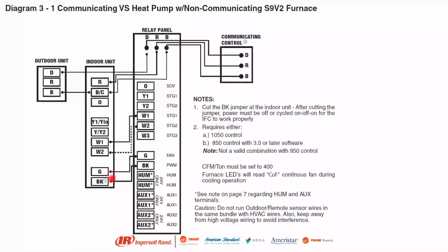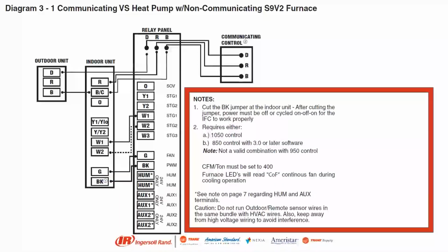Here's our S9V2. We have to energize this BK terminal and then cut the BK jumper. We have to do that at the indoor unit. What it does if we do not connect that BK terminal is the furnace will not ramp up with the compressor. So we'll ramp to 80% and the fan speed will still be at 50% and we'll trip out on high head. So we have to cut that BK jumper in order for the compressor to operate the indoor fan speed. So if the compressor is running at 80%, the fan speed is going to be somewhere near 80%. So please always connect that BK and cut the BK jumper.